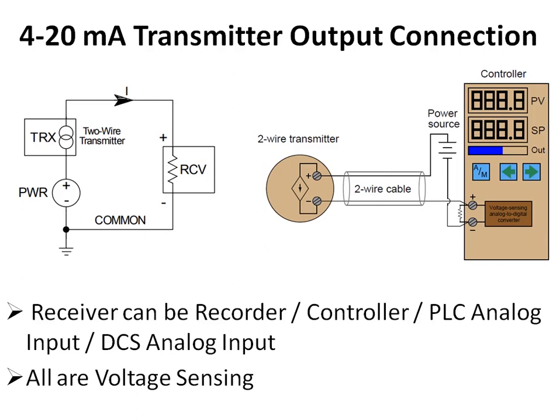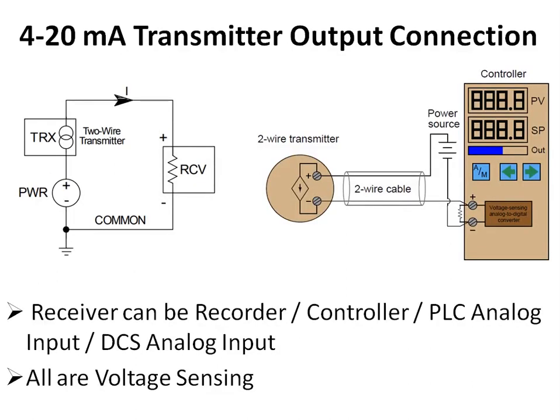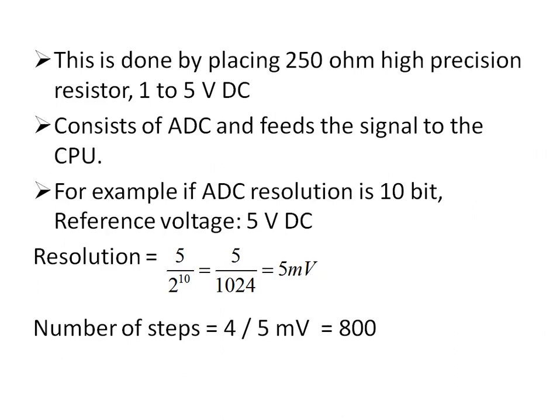This current-to-voltage conversion is done using a high precision resistor, which converts the 4 to 20 milliampere signal to a 1 to 5 volts DC signal. This 1 to 5 volts DC is then converted to a digital signal using an analog to digital converter, an ADC. The digital signal is then fed to the CPU, the central processing unit, which takes the final decision.